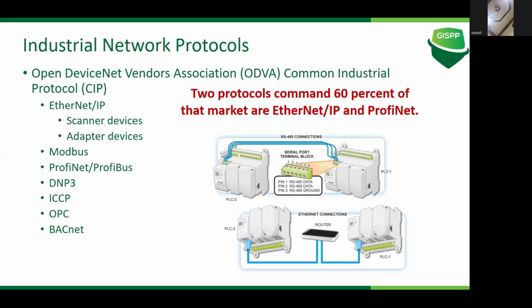Now SCADA needs to talk to this equipment. Those equipment have a certain pre-built protocol in which they send information on the field bus. You remember the field bus, the main road where all SCADA devices were connected. So, say I have a device that is NERC compliant and only understands DNP3. Now I will configure my SCADA system to understand that protocol. SCADA is collecting certain information from DCS through Modbus. So as a SCADA, I will understand the Modbus information, convert it into something SCADA can understand, and then convert it into DNP3 language. So it will be sent to that particular electrical grid OT device.